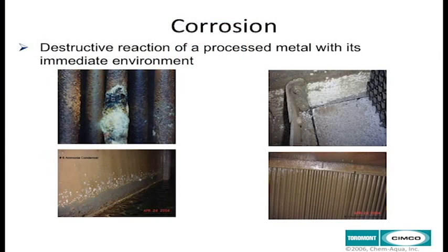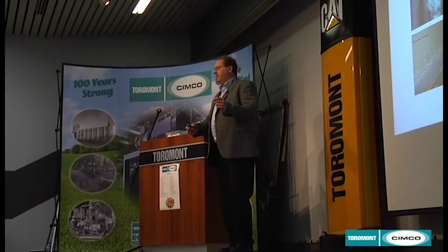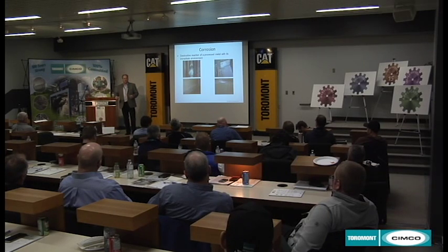There are many attributes to corrosion, especially when you start up a new cooling tower. There's a procedure called passivation. Passivation is very critical to the initial state of your new cooling tower. With old evaporative condensers 20, 25 years ago, the amount of galvanizing on the cooling tower was pretty thick, and you could get away without passivating. But with the new technologies in new evaporative condensers, the galvanizing process is very thin and very susceptible to corrosion.